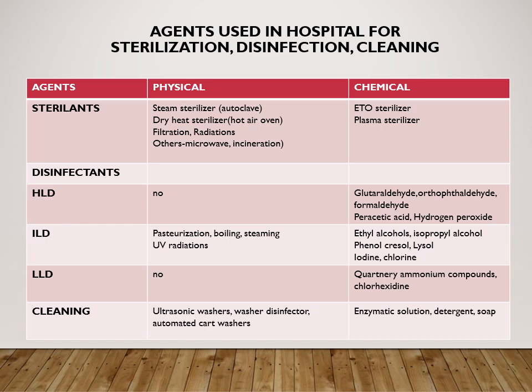Intermediate-level disinfectants include physical methods such as pasteurization, boiling, steaming, and UV radiation. Chemical intermediate-level disinfectants include ethyl alcohol, isopropyl alcohol, phenol, cresol, lysol, iodine, and chlorine. Low-level disinfectants are chemical only — quaternary ammonium compounds and chlorhexidine, which is commonly used in mouthwashes. Ethyl alcohol and isopropyl alcohol are very important groups to remember. For cleaning, ultrasonic washers, washer-disinfectors, automatic washers, enzymatic solutions, and detergents are used.